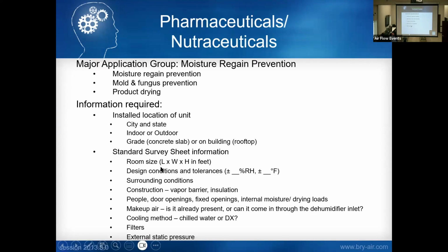Pretty common feature. Is there a purge segment or something for cross contamination between the air streams on your wheel? No, not on these applications. We haven't run into where we need it. We really don't see much cross contamination on the desiccant rotor.